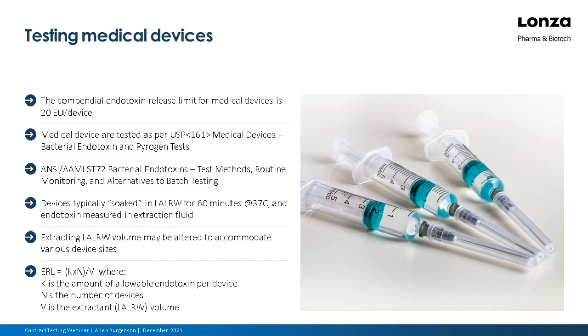And for these assays, the devices are typically soaked in LAL reagent water for 60 minutes at 37 degrees, and the endotoxin is measured in the extraction fluid. The extracting LAL reagent water volume may be altered to accommodate various device sizes. So it makes very little sense to use a full 40 mLs for a tiny device, nor does it make sense to use 40 mLs for a huge medical device.